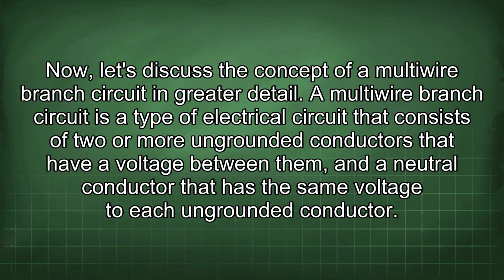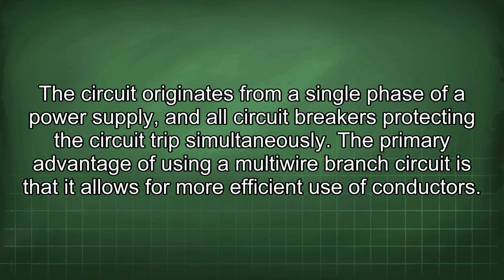Now, let's discuss the concept of a multi-wire branch circuit in greater detail. A multiwire branch circuit is a type of electrical circuit that consists of two or more ungrounded conductors that have a voltage between them and a neutral conductor that has the same voltage to each ungrounded conductor. The circuit originates from a single phase of a power supply, and all circuit breakers protecting the circuit trip simultaneously.